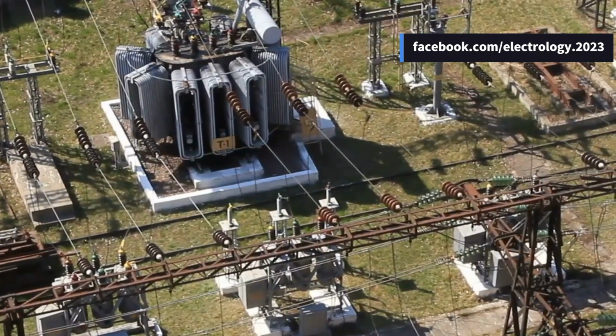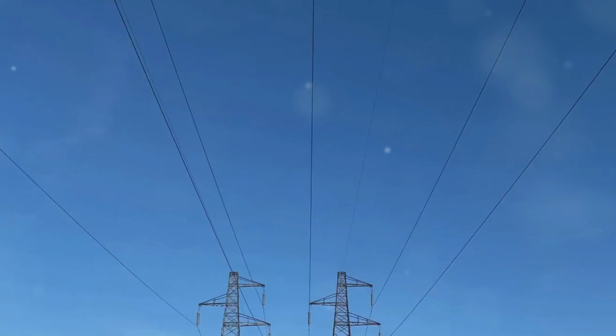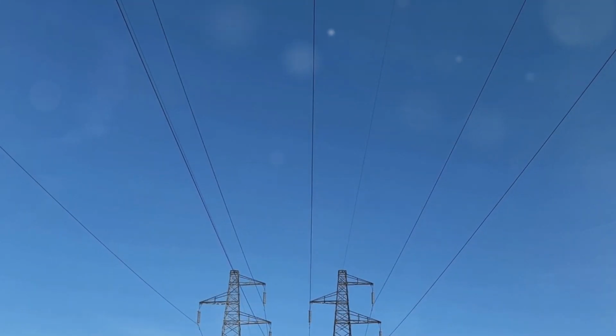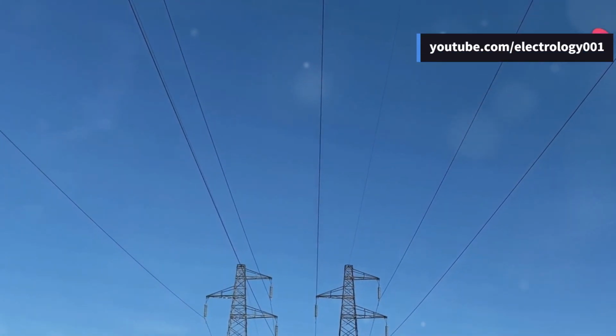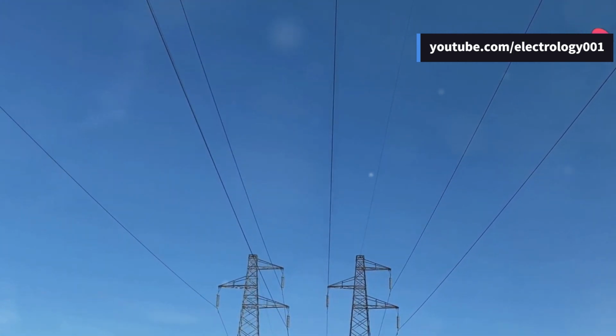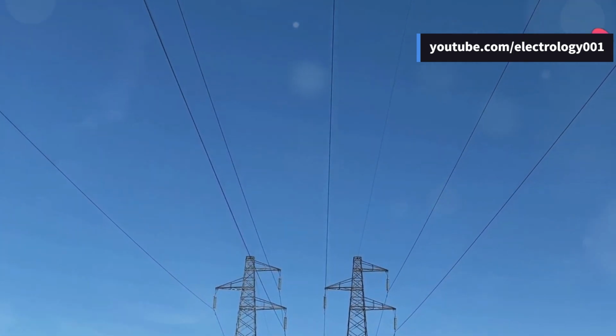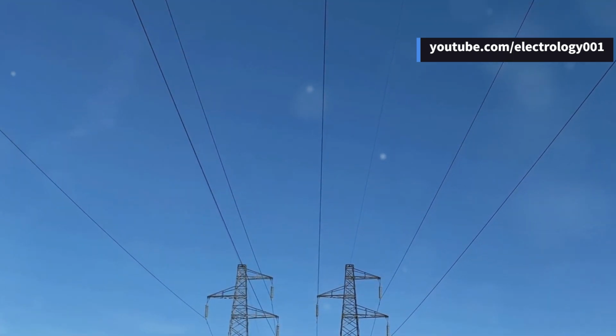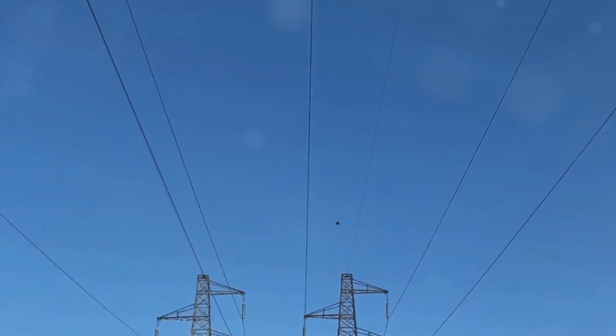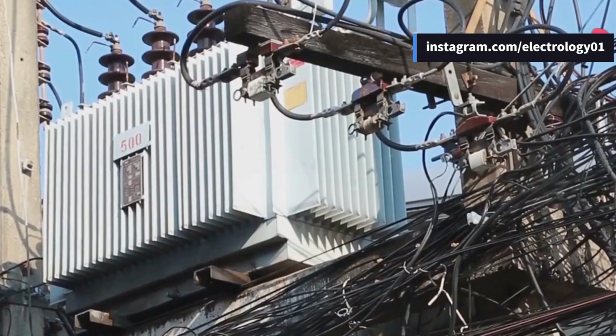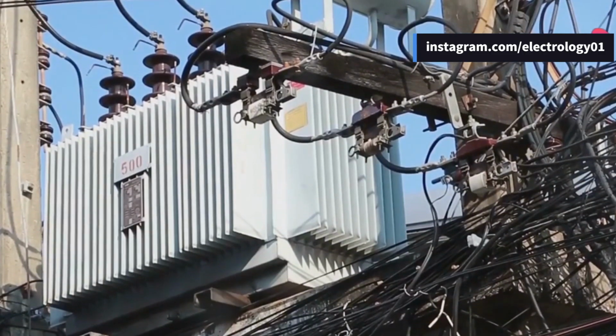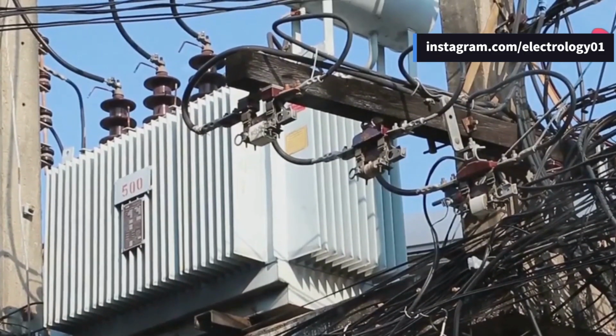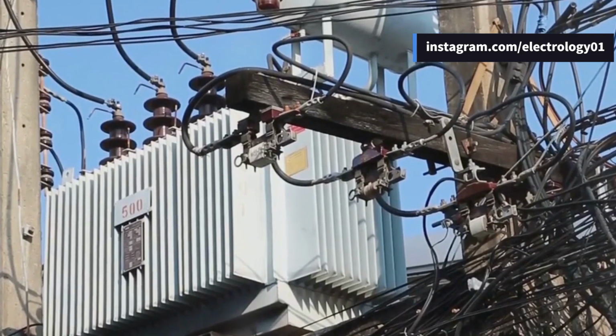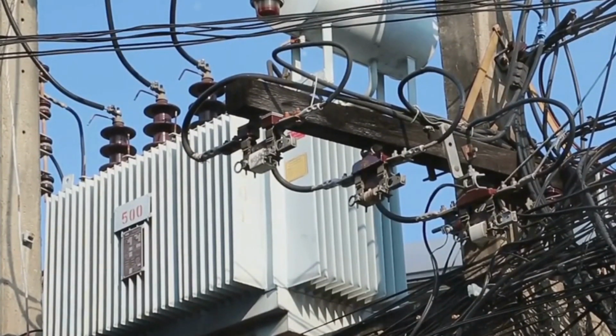But why exactly is the parallel operation so beneficial? And how does it offer such astonishing advantages? Let's unravel this fascinating mystery and also explore the conditions necessary for these parallel operations to work effectively. Imagine two or more transformers running in parallel. For optimal performance, they need to satisfy several key conditions. They must have the same voltage ratio, the same percentage impedance, the same polarity, and the same phase sequence. Let's dive into each of these conditions in greater detail.